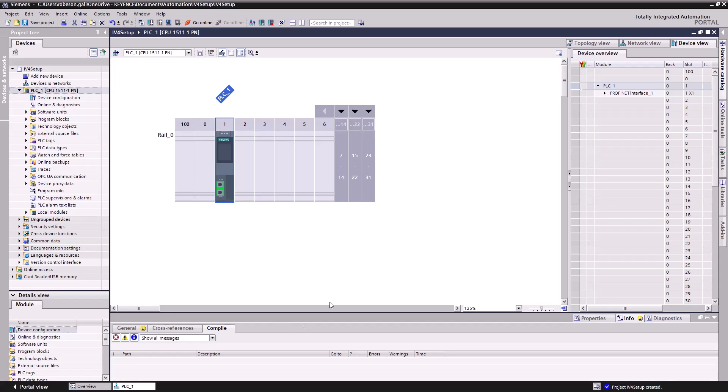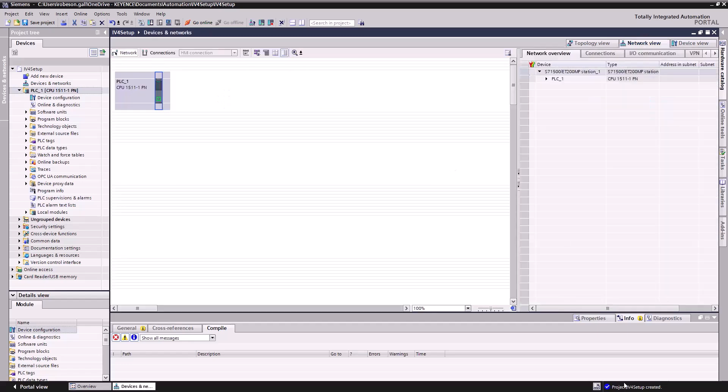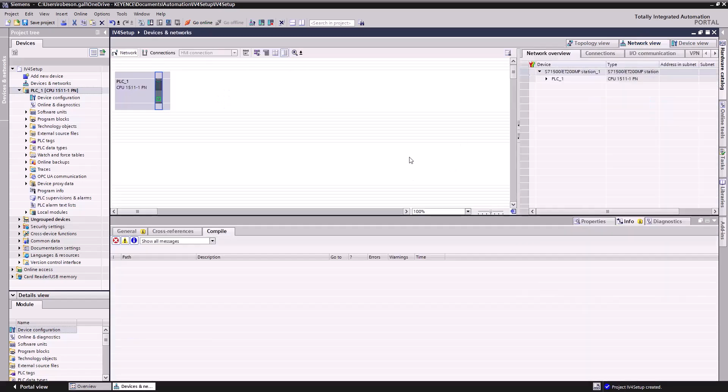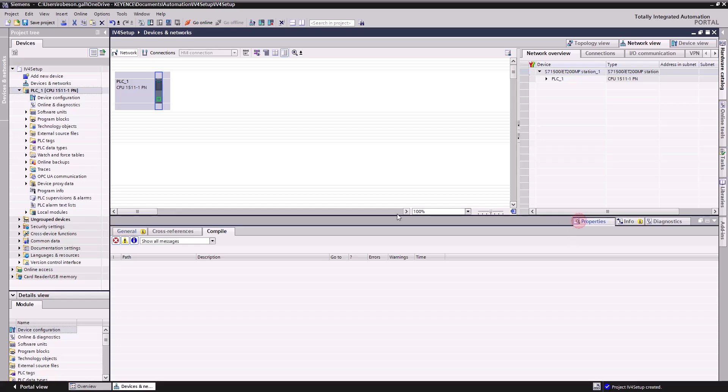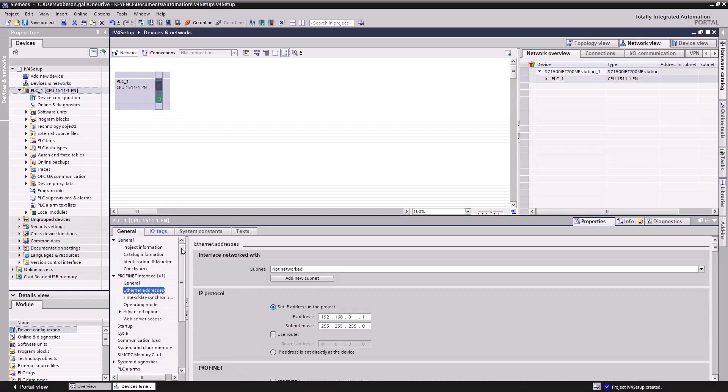From here we'll want to do one thing. So I'll go to network view and kind of show you this. The network view screen is very nice because it shows us all our devices all together. I'm going to go to properties. This is the properties of the PLC we have selected here. It's going to take us immediately to this Ethernet addresses subcategory. You'll see the subnet is not networked. We're going to need to add a new subnet.